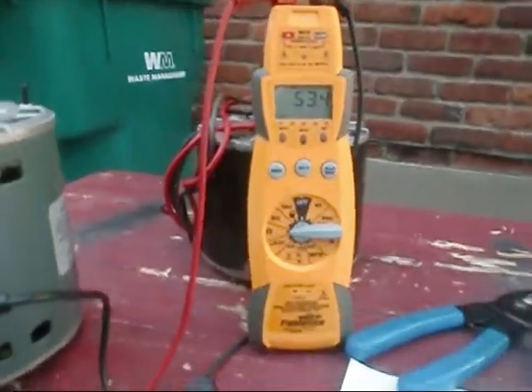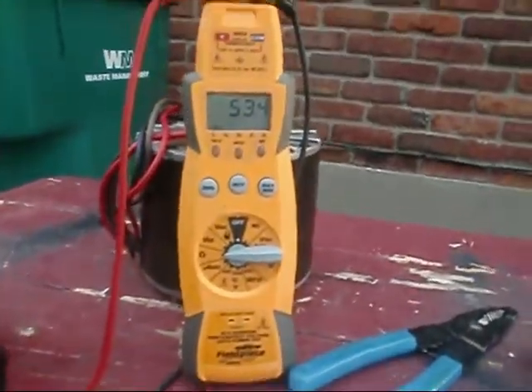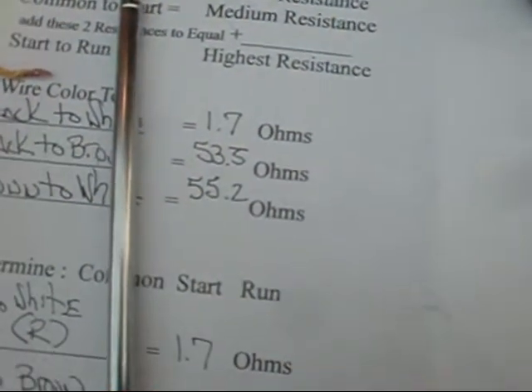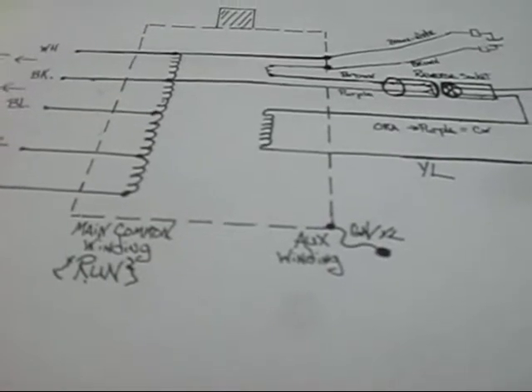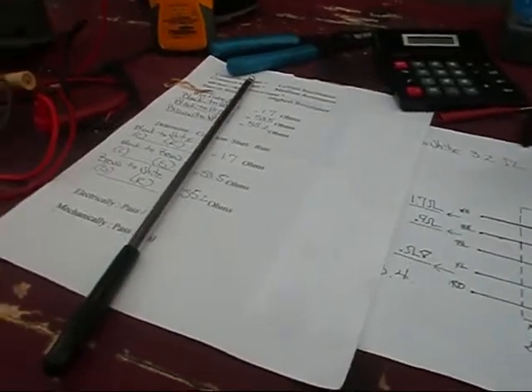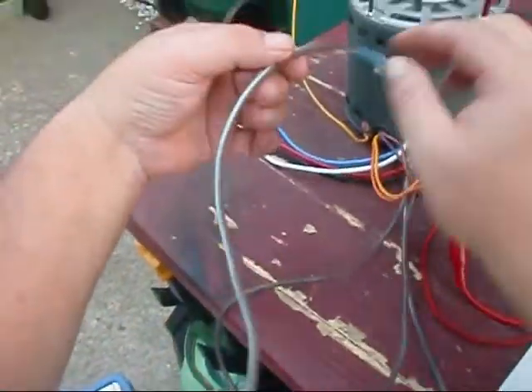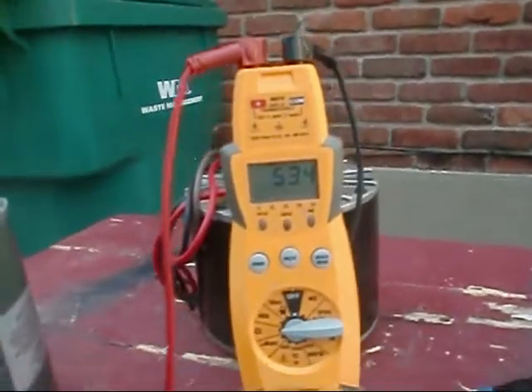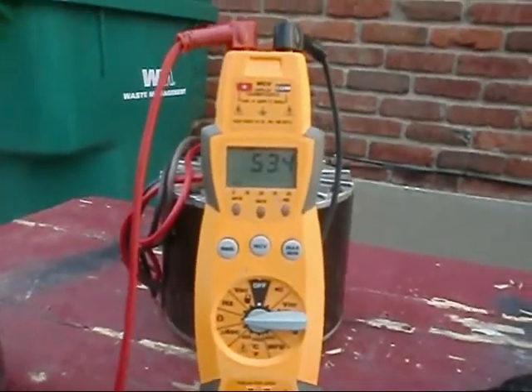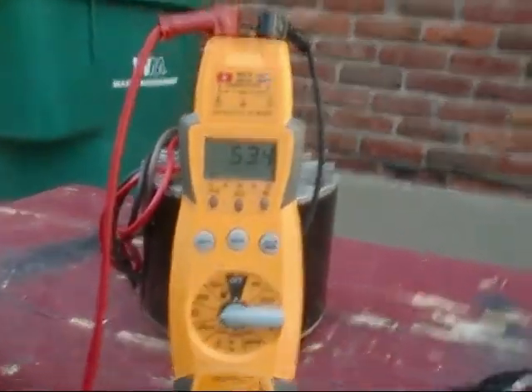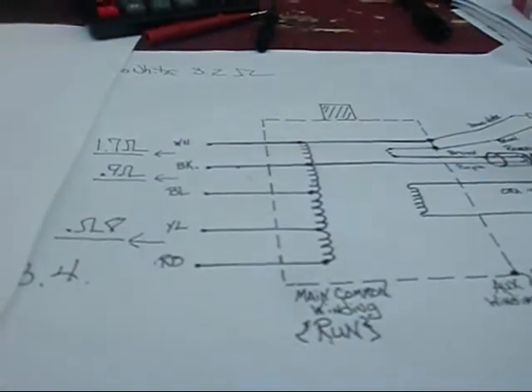We're looking at 53.4. Where's that on here? That looks like that's common to brown. What's common to brown? That's common to start. This is the auxiliary windings. This is the start winding side of the motor. Now, it doesn't matter whether or not we take the capacitor out of the loop. You know how we tie in our brown and white and our solid brown? Doesn't matter. It's still the same. This is this side of that motor. But, man, guys. I hope y'all got something out of this. I love doing these. And I appreciate all my good friends and buddies chiming in and everything.